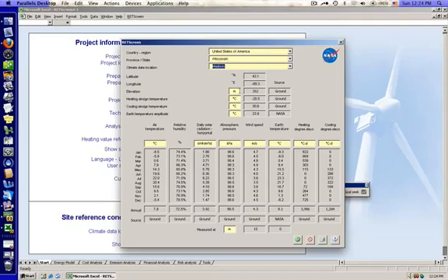It's not going to make a huge difference, but you can see right on this page what numbers RETScreen is using. So they give you a relative humidity, for instance, where if you have cloudy mornings, the relative humidity will tell you something about that fog. Daily solar radiation is what we are really interested in. And I'll talk about this input when we look at the shading analysis. It breaks out the daily solar radiation by month, January, February, all the way to December, just like the Pathfinder does. So we can use this to evaluate shading. What it doesn't have is an hour by hour, so we're not able to assess the solar radiation in the mornings versus the solar radiation in the afternoon.